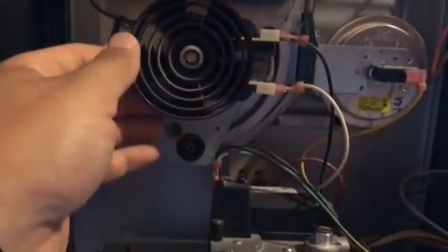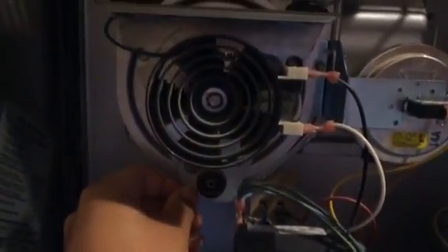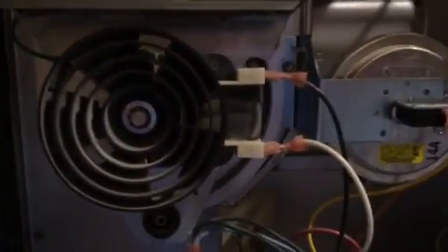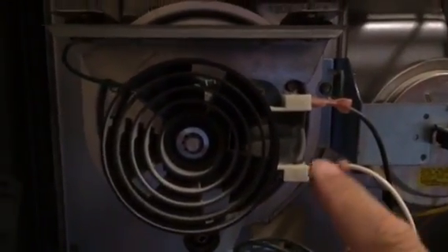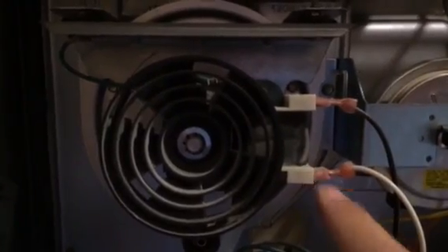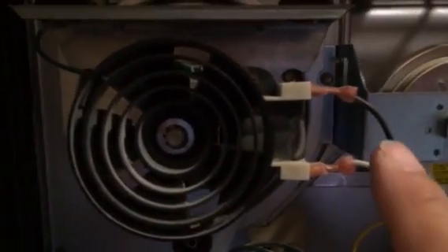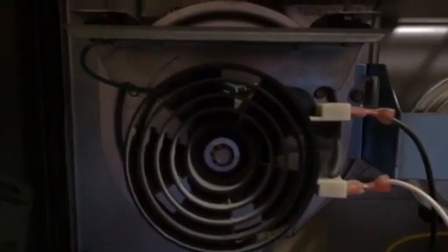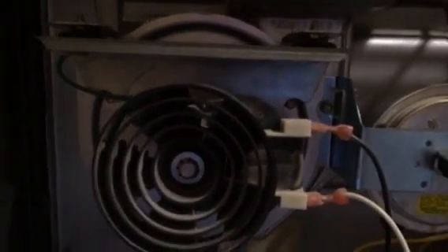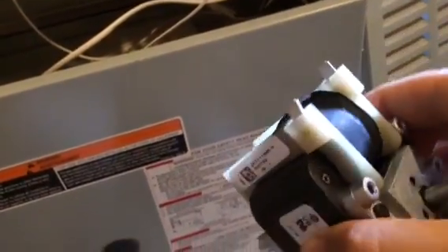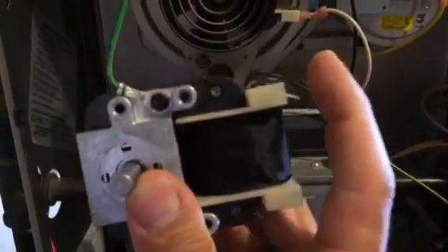Now I removed the first screw. It appears to be getting loose. A good point to remember right now is that you just want to remember what wire goes on what terminal. So we'll just remember that white wire goes on the bottom terminal, black wire on the top terminal. Alternatively, you can mark them on the new motor. This being the new motor. The terminals are located right there. So this is going to be mounted like so. White on the bottom, black on top.